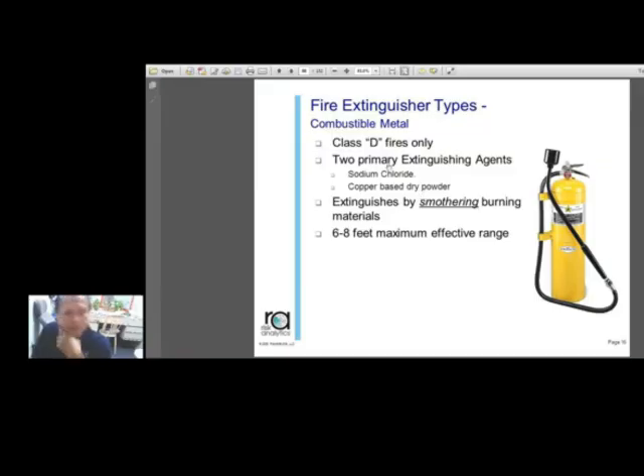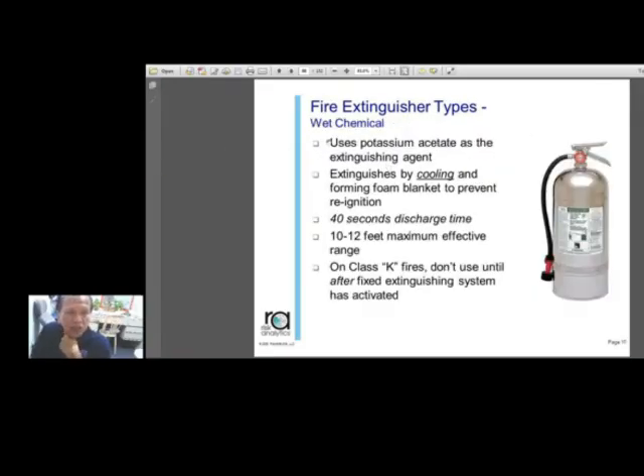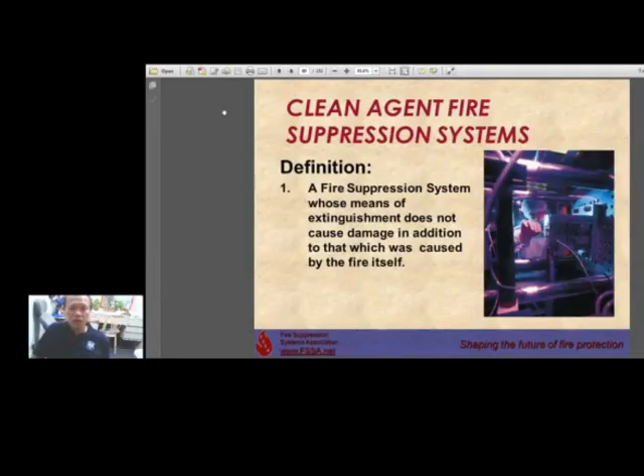Okay, the metal fire. Then fire extinguisher types: wet chemical uses potassium acetate as the extinguishing agent, extinguishes by cooling and forming a foam blanket to prevent reignition. 40 seconds discharge time, 10 to 12 feet maximum effective range, so it's a little farther than the yellow one earlier. On Class K fires, don't use it until after the fixed extinguishing system has activated. So there are some conditions on its use.